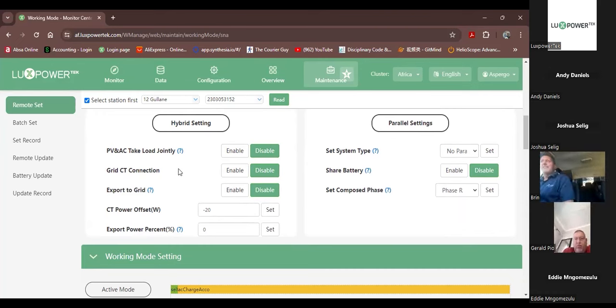You know, we have some prepaid meters that are very, very sensitive to leak current. Especially if you have a machine that doesn't have an external CT, then you're going to want to use your CT offset here. What I like about this is that they've grouped everything together. Before, we had to go and search for these settings in various places on the page, but here it's grouped together very nicely. This PV and AC take load jointly.